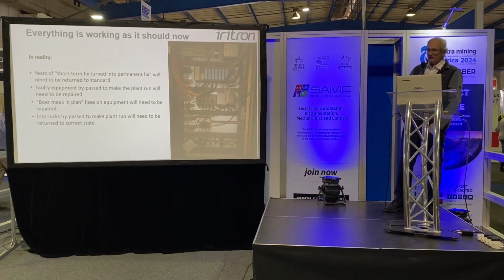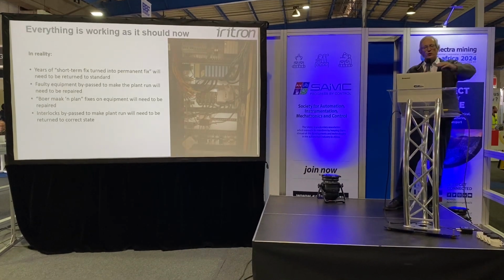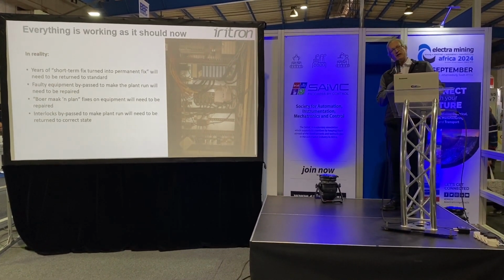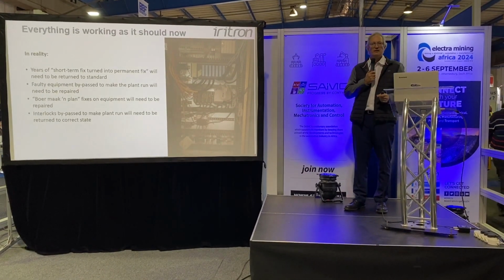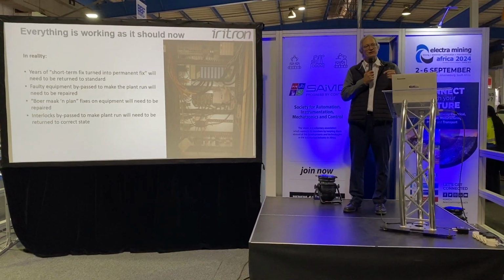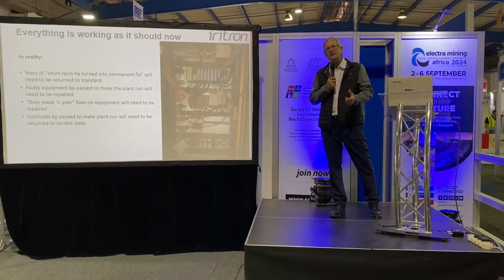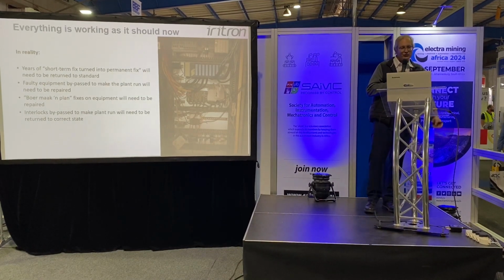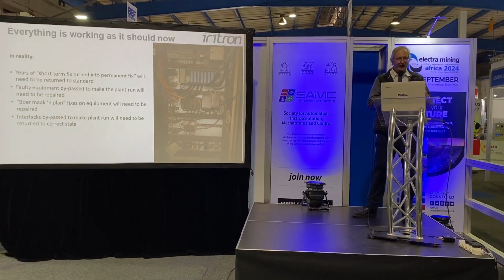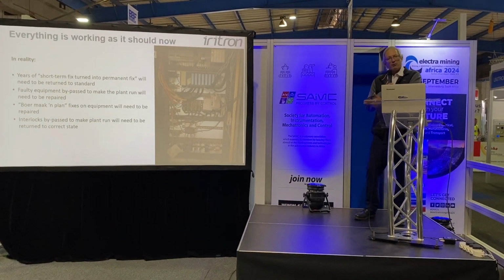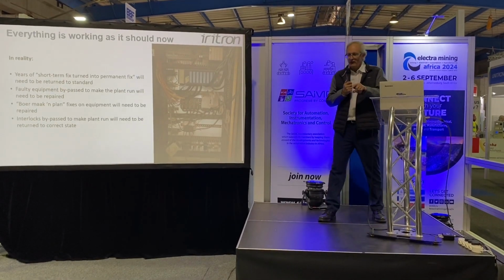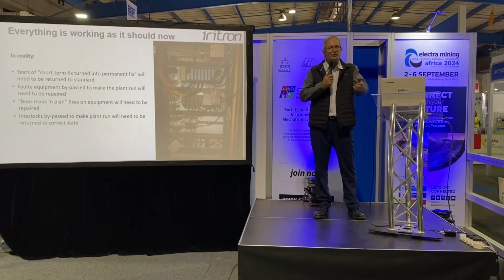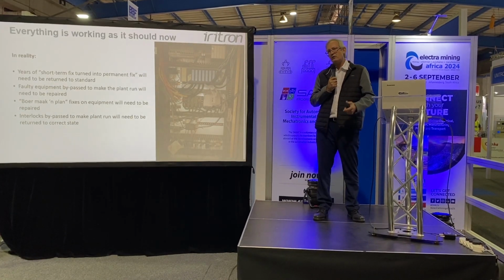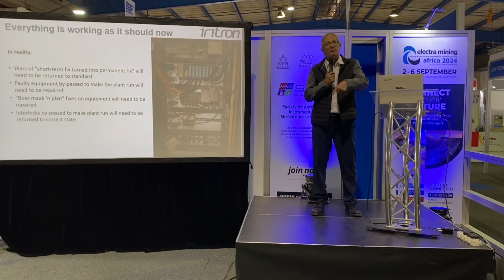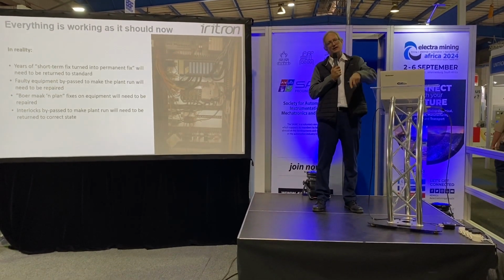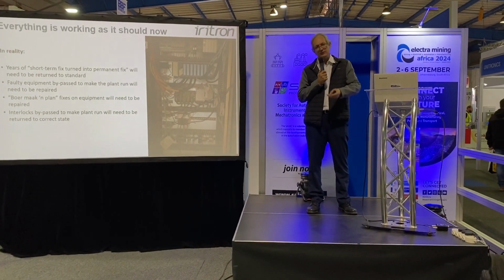So in reality, what happens, like in the previous picture, is years of short-term fixes that turned into permanent fixes. The short-term fix that's been there for the last 10 years will now need to be fixed, because we're actually changing the control system, we're upgrading it, and we need to include that into making the process actually operate as it should. We found that, for instance, people bypass equipment to make the plant run, which is also a short-term fix. We're getting this intermittent contact on one of our emergency stop buttons, and we can't get the plant to start because this thing trips the whole plant the whole time. So let's just bypass it and we'll fix it tomorrow. And then 10 years later, when you do the project, you have to fix it because you touched it.